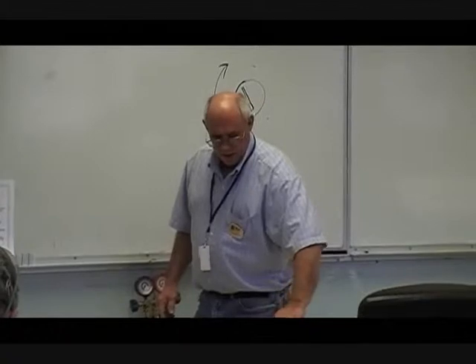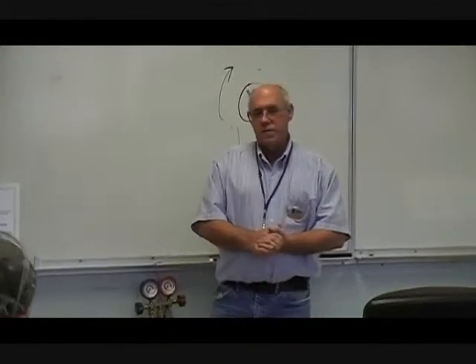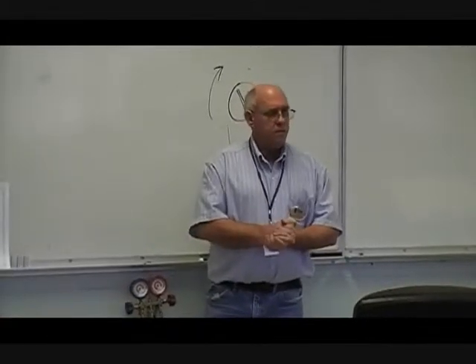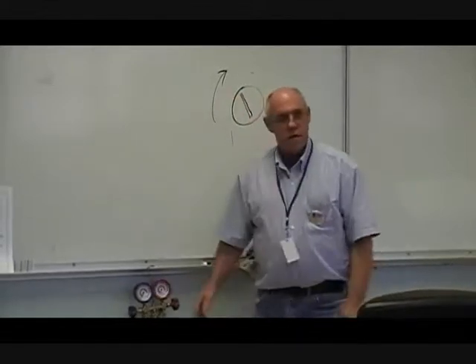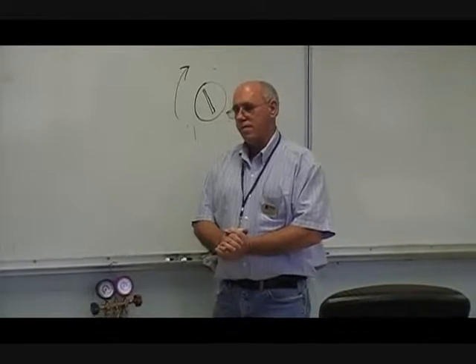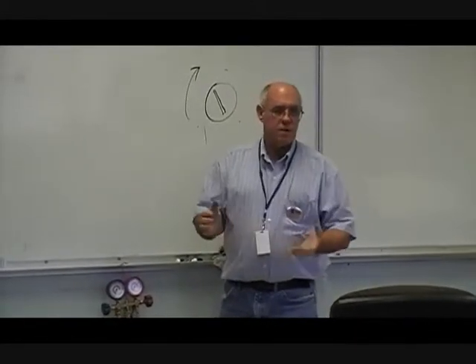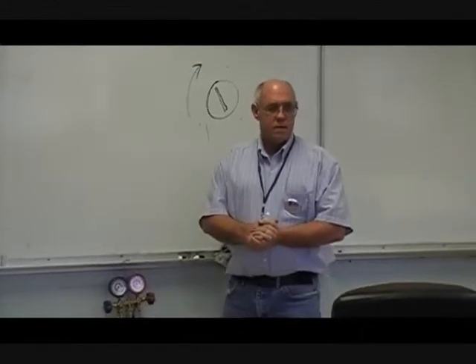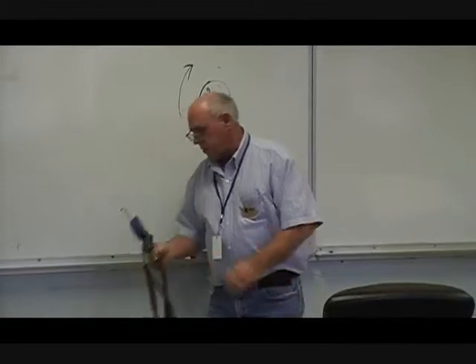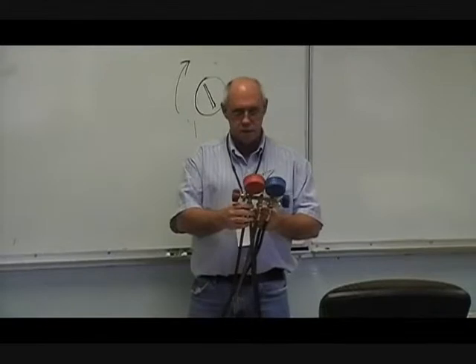The 410A has changed a lot of the ratings of the tools that we use today. So when you're out there in the field, it's so easy to grab another set and not realize that you may be working with a set that's not rated for them. Be careful on that, okay? The fittings are the same. I mean, as far as going up to a unit, one of the quarter-inch flare fittings or hoses will fit in one, so be careful on that. Make sure you know what you're hooking up to.